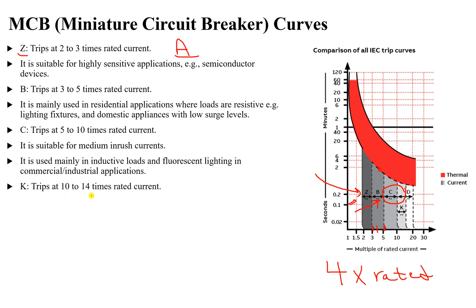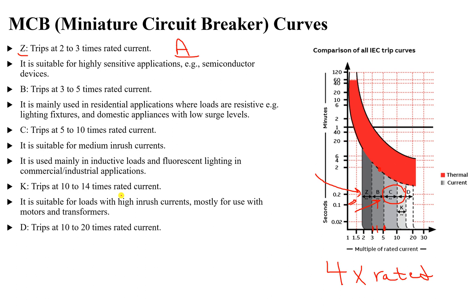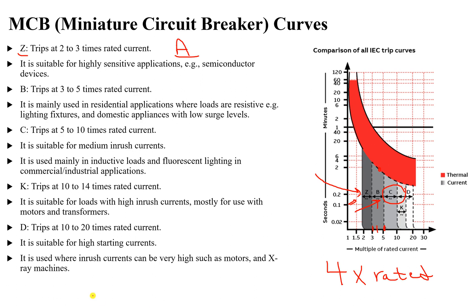Type K operates between 10 to 14 times the rated current, and type D operates between 10 to 20 times the rated current. Both K and D are used for loads with very high inrush or starting currents, such as large transformers, large generators, large motors, and X-ray machines. To prevent the circuit breaker from tripping at startup of these loads, we use type D or K trip curves.